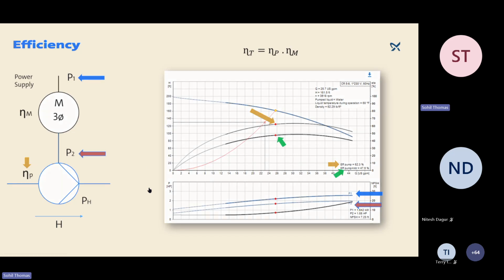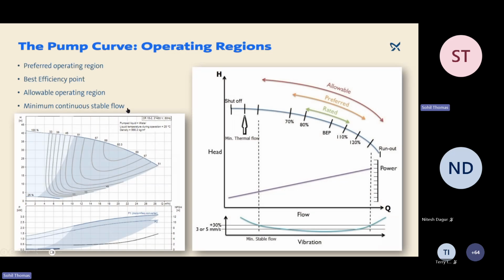So that's a snapshot of a small pump curve, what you can see on the screen. We always want to run the pumps at the best efficiency point over here, but that's not the case in normal conditions. You won't be able to run those pumps continuously at the best efficiency point. But the main aim is to run close to that so that the efficiency is the highest and the vibration is the lowest at that point. So the main goal is to operate around that region so that we get maximum reliability for the pump, and the energy savings are also at the highest level.